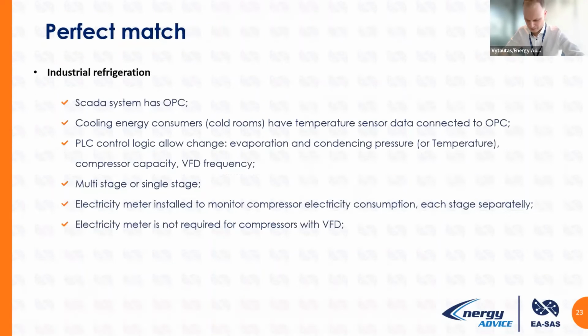So, a perfect match. How to understand quickly whether our system is suitable for your application? Of course: does your SCADA have OPC, if it's an industrial application? Do your cooling energy consumers have temperature sensors, and are these sensors connected to OPC, to SCADA? Do you have this data? Does the PLC control logic allow changing some parameters, such as evaporation and condensing pressures or temperatures? Can we change compressor capacity? And can we change the variable frequency drive compressor frequency? If yes, then we can install.